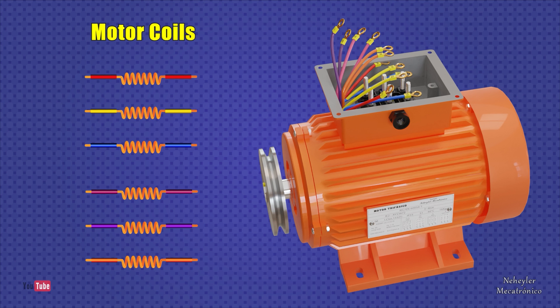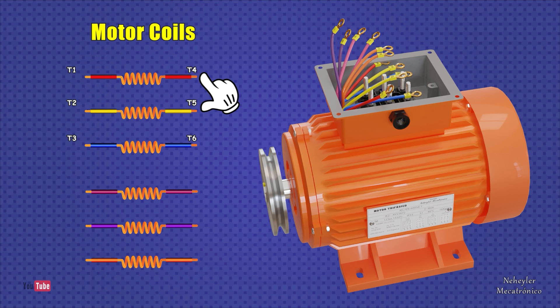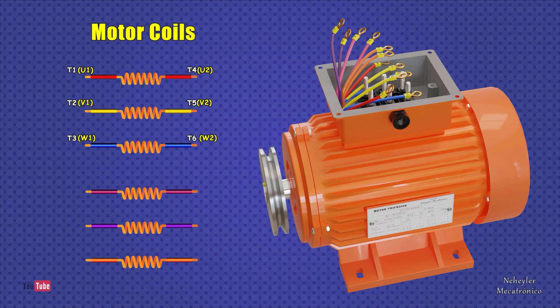Let's pay attention to the terminals of the first three coils. It is usually designated from terminal 1 to 3 on one side. At the other end of the coils they are named from terminal 4 to 6 if based on the NEMA standard, or have letters U, V, and W if manufactured under the IEC standard.